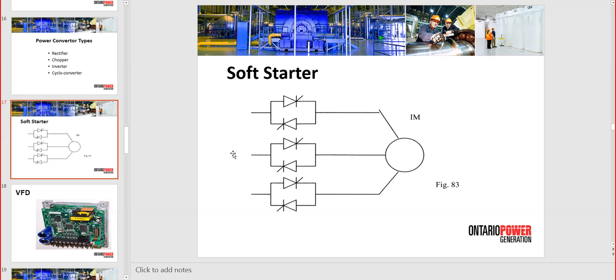So it has thyristors, or for low power you can have 2 thyristors in one device. This one is operating as a transformer would; it is not changing the frequency on the motor, it is changing only the voltage. On low power, those are called triacs, with two SCRs or thyristors in anti-parallel in one device. So what do we change? Voltage. Do we change the frequency? We don't. Therefore, a soft starter cannot have large torque. Remember, the torque is proportional to the square of the voltage. So when we start with low voltage, there is almost no torque.